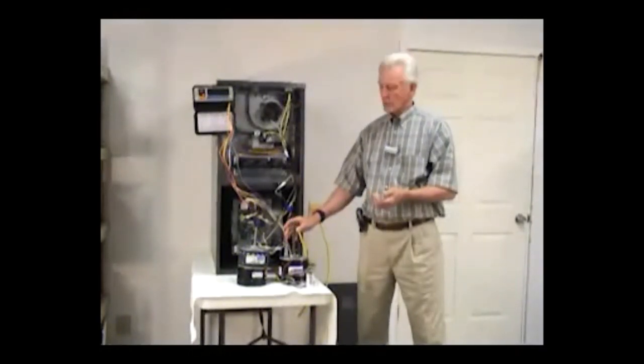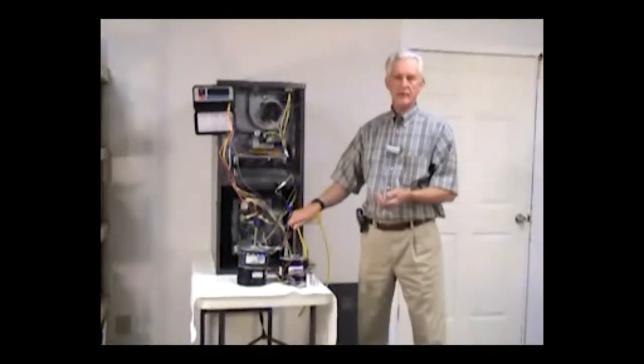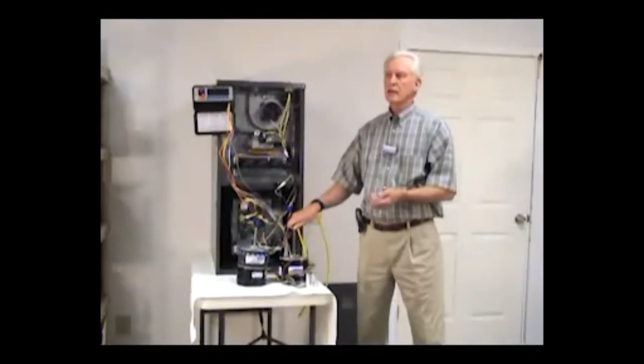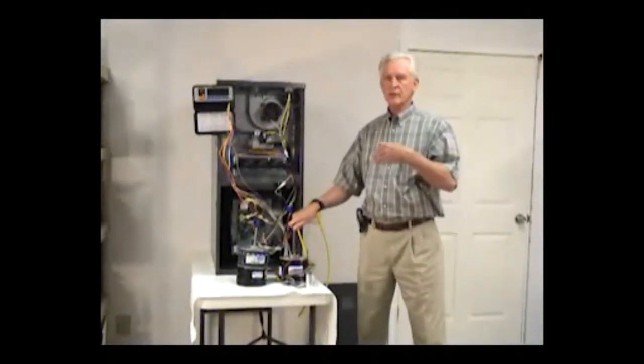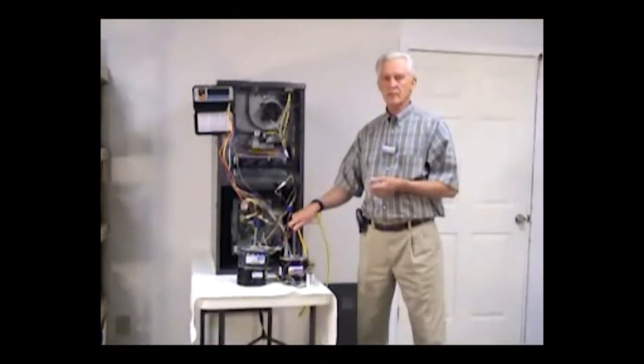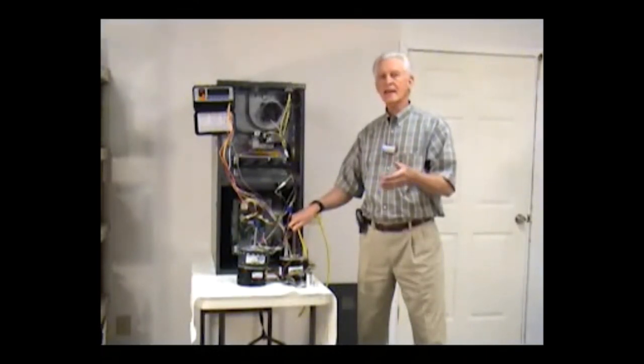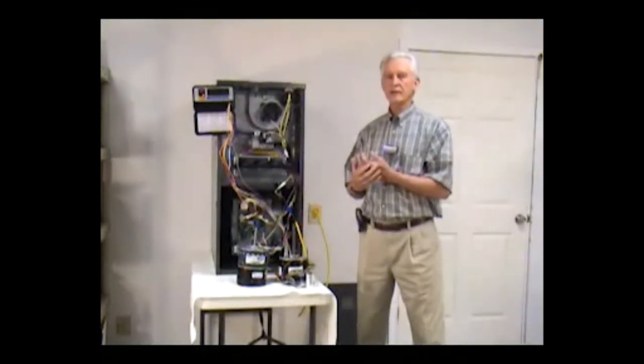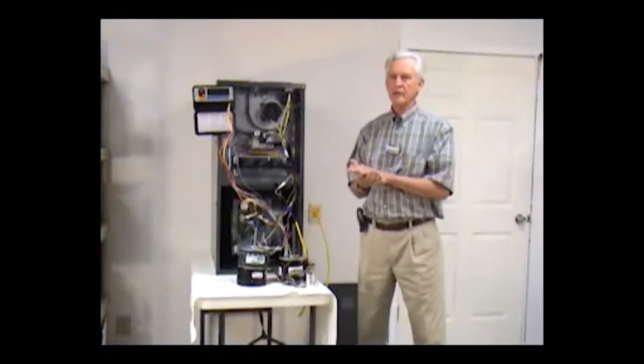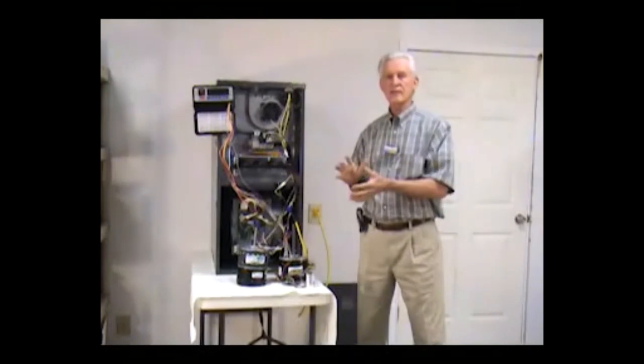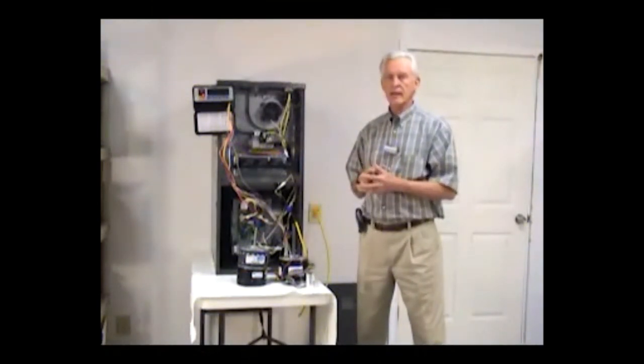The external static pressure put against this motor is going to create, for all intents and purposes, the load that that motor has on it. What happens with a split capacitor motor, PSC, is that as we increase that load against that motor, if you want to call it load, then that motor will actually produce less and less CFM at a given static, which manufacturers will typically use 0.5 inches of water column for the range that this motor will operate in, and up to.